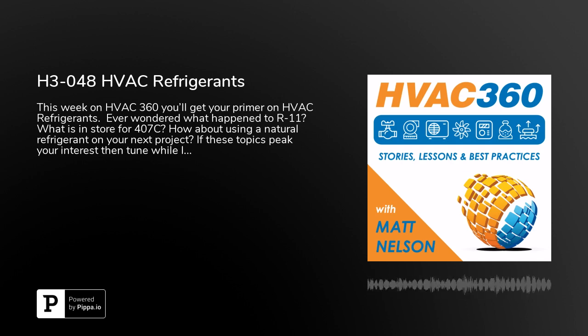From a practical standpoint, with R11 or R12, if there was a leak in an R12 system you could just add more R12 and be fine. Whereas with 410A, you'd really have to take everything out and put a whole new mixture back in, because it's a combination of multiple different refrigerants.